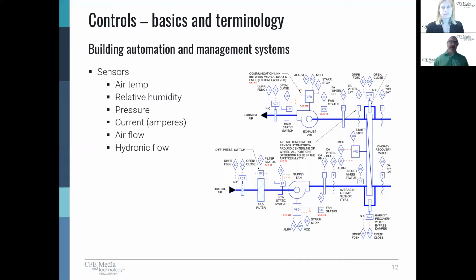So shown here on the right is an example of a control diagram. And here we have inputs and outputs, and we have sensors. So as shown here, we might be interested in air temp for a fan. We might be interested in humidity with how we're going to control our humidifier itself. We can even look at current, so we get status on whether or not a motor is running. We could do switches for whether or not we have an end stop. All of these are what the system is going to use to start performing calculations or start relaying the information on how the system's actually behaving.